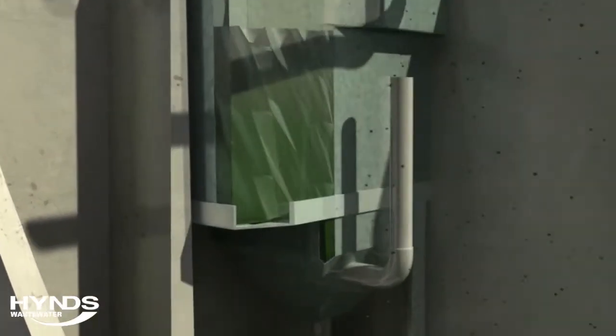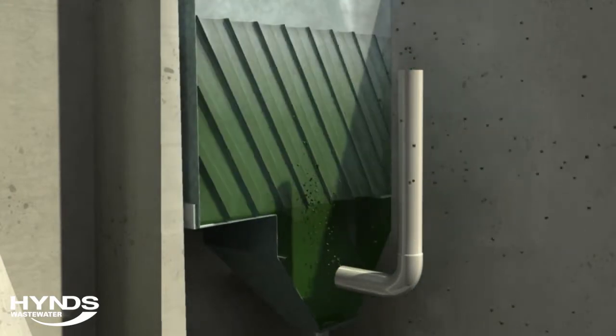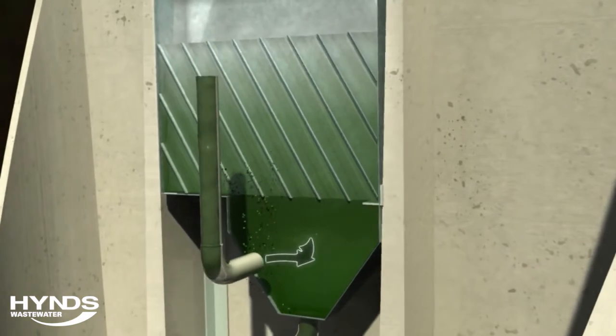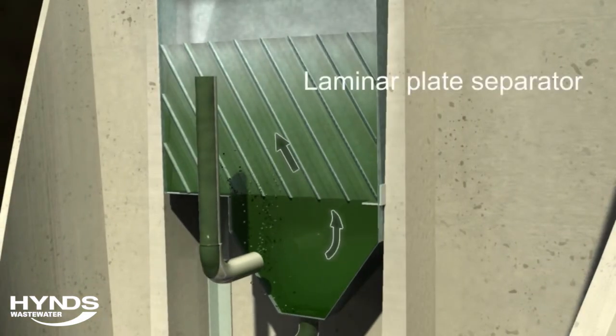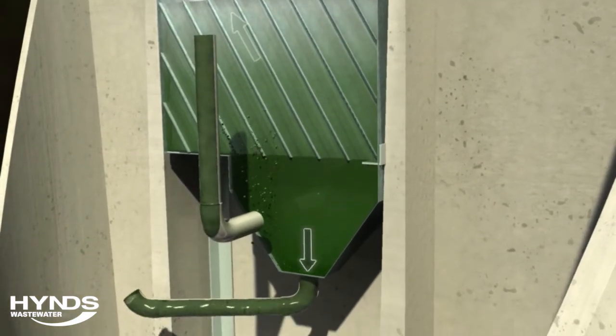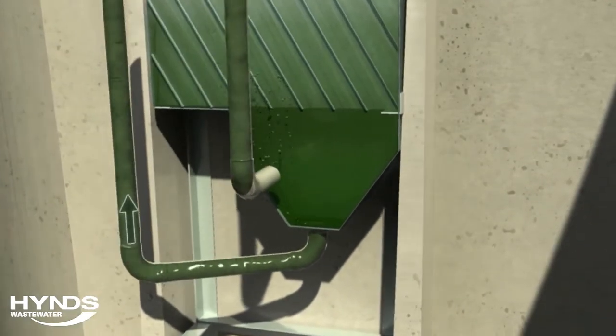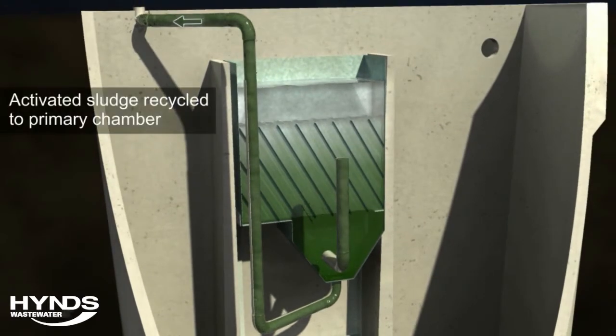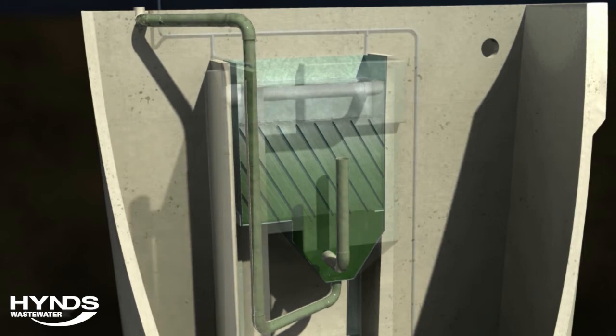Once the water has passed through the second stage of filtration, it enters an advanced separator, where a series of laminar plates filter the remaining solid particles from the clean water. These particles drop to the bottom of the separator, where a venturi or suction system constantly sends water from the bottom of the separator back to the inlet of the primary chamber. This function recycles the water back through the system approximately three times per day.